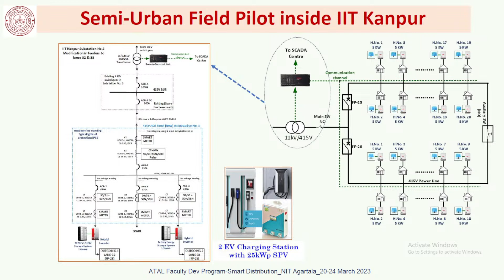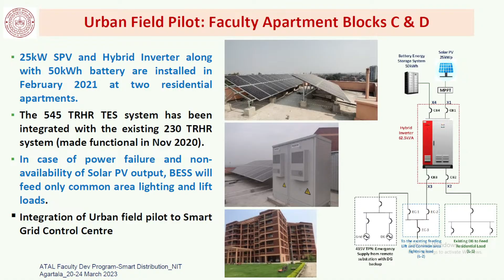In the urban housing complex, solar has been put in, but at a smaller size due to fund availability: 25 kilowatt, with a load of 75 kilowatt. Then a battery of roughly 50 kilowatt, 100 kilowatt-hour has been put in—so 50 kilowatt-hour. These are two housing complexes we have covered. The idea is that if solar and battery are there, they can take the load completely. But if grid power is not there, at night time, if only storage is there, we only meet emergency load, like area lighting and lift load, which otherwise would be fed from a diesel generator. So we want to avoid the diesel generator—that's the application.